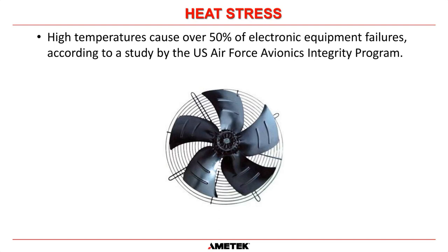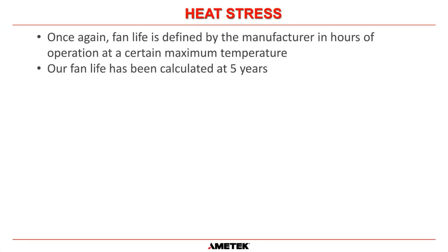Also, heat stress is extremely important for electronic components. High temperature causes over 50% of electronic equipment failures, according to a study by the US Air Force Avionics Integrity Program. 50%, so one in two failures during that US Air Force study showed that high temperatures had some effect on the failure. So that is why the majority of our UPSs have fans in them, is we want to get that heat out of our UPS so we don't have any temperature related failures.